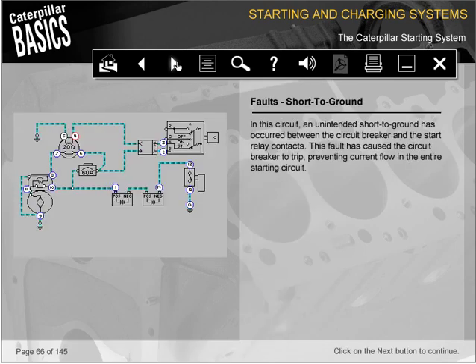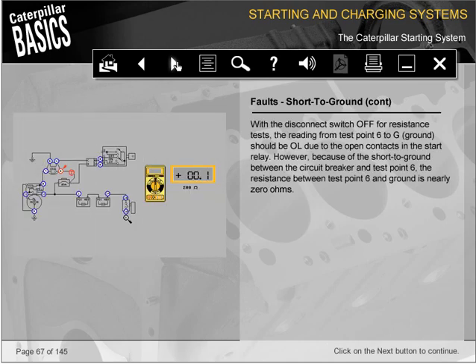In this circuit, an unintended short to ground has occurred between the circuit breaker and the start relay contacts. This fault has caused the circuit breaker to trip, preventing current flow in the entire starting circuit. With the disconnect switch off for resistance tests, the reading from test point 6 to G, ground, should be OL due to the open contacts in the start relay. However, because of the short to ground between the circuit breaker and test point 6, the resistance between test point 6 and ground is nearly 0 ohms.